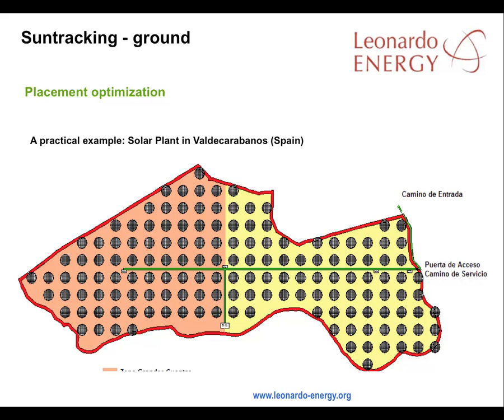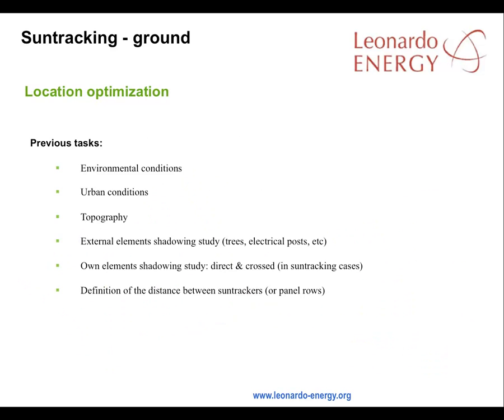Over the next slides, we will refer to a solar plant built at Val de Carabanos, south of Madrid in Spain. Prior to settling on a location, a series of investigations had to be made into the environmental and urban conditions, including air pollution levels. The topography has to be studied, taking account of shadowing issues and the area that will be needed for panel rows, whether fixed or sun tracking systems are used.